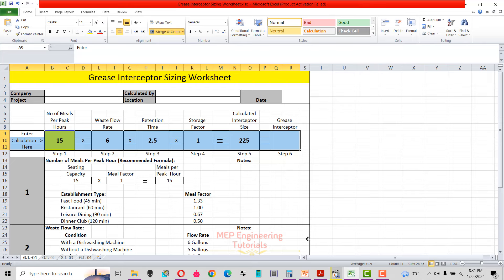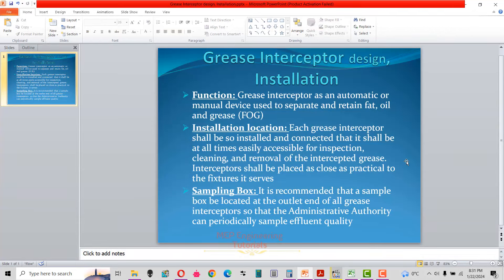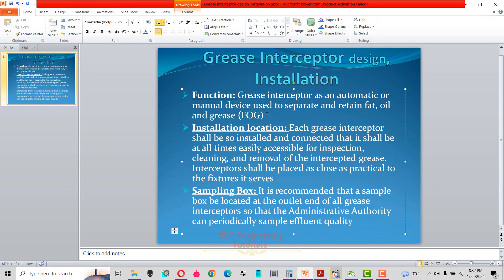Before proceeding with the calculation, I want you to understand what a grease interceptor is and how it works. Let's go through this PowerPoint slide. Basically, a grease interceptor is an automatic or manual device used to separate and retain fat, oil, and grease — also known as FOG. It prevents FOG from entering the outlet pipe. Due to buoyancy effect, fat, oil, and grease accumulate on the surface of the water, while solids settle at the bottom, and water flows to the outlet pipe.